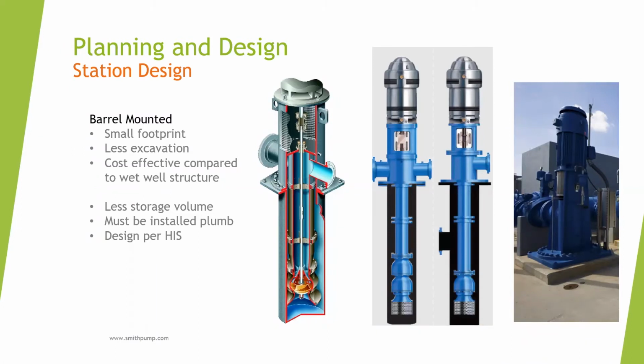So let's talk about the 2 vertical turbine pump arrangement options, barrel and wet pit. Barrel mounted pumps can draw water from above grade or below grade, depending on the piping setup. These pumps have a few advantages over wet pit pumps. They have a smaller footprint, generally less expensive to excavate, and are cost effective. However, they do have less storage volume and require a separate water storage tank to feed them. The barrel must be installed plumb for maximum pump life, and barrels have a specific design requirement by the Hydraulic Institute standards that should be followed.